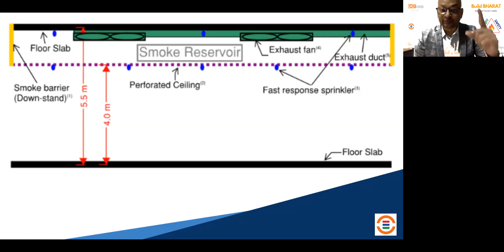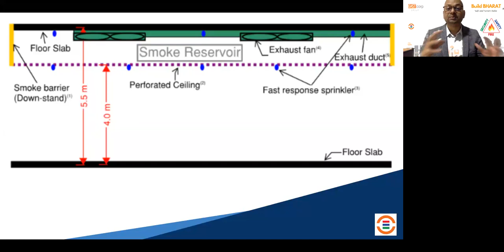But suppose your sprinkler isn't talking to the ventilation and works independently - it will wait for smoke to accumulate until it reaches 68 degrees, then discharge. By that time, if you switch on the ventilation system, it will be ineffective since the smoke had already spread. You won't have effective ventilation possible in a water discharge scenario. So you need to ensure the integration works in a way that is not conflicting, but complementing.